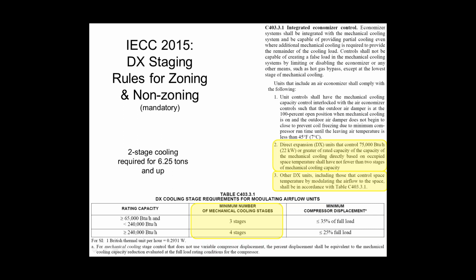So specifically, 65,000 BTUs, which is what, a little more than 5 tons. So we'll just say six tons, 5.5 tons. You have to have 3 stages of cooling. And if it's even bigger, 240,000 BTUs, which is a 20-ton unit, you are required to have a minimum of 4 stages of cooling. So I know that's not the controls guy's problem per se, right? Whoever's doing this controls work. But as soon as you put a zoning system on there as the controls guy, you should be telling whoever's doing the mechanical equipment, hey, I need to have 3 stages or 4 stages. Otherwise, we're not going to, as a group, get this thing to comply.